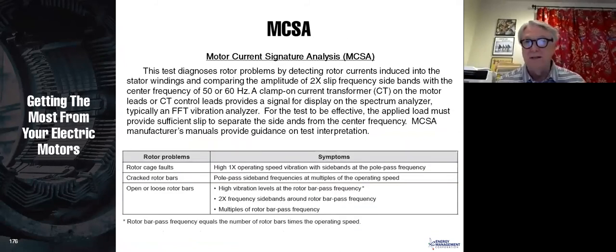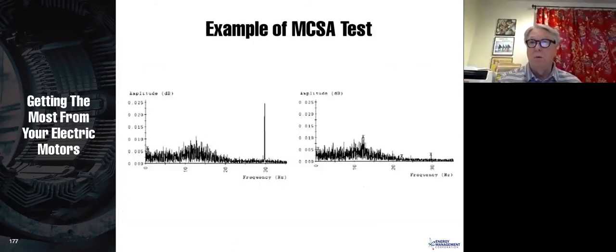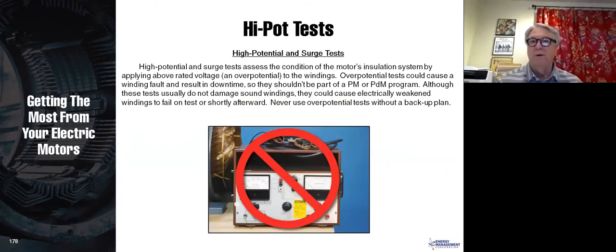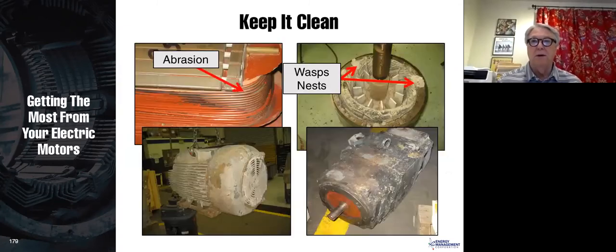This is a fancy one called the motor current signature analysis, a device that looks at the motor current and evaluates the signature and determines whether the motor is having problems. This is not just for bearings, this is for the whole motor. This is an example of an MCA test. Doesn't look very obvious there, but if you have an MCA tester, then that's pretty fancy stuff that we're able to do these days. There's a hi-pot test, talks about how to do that.